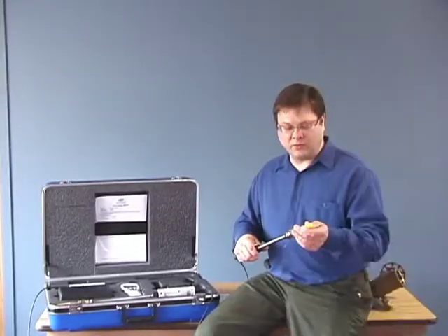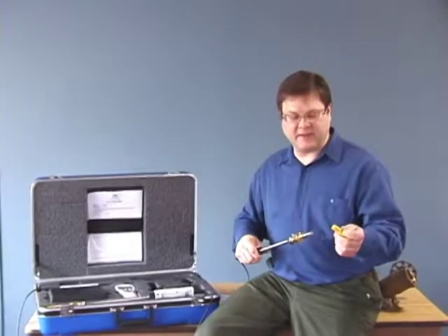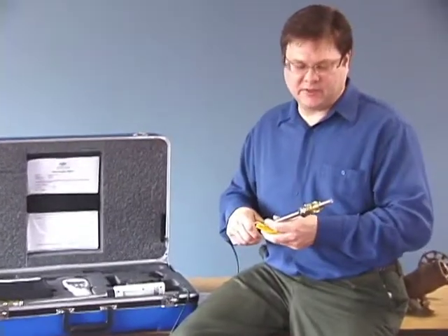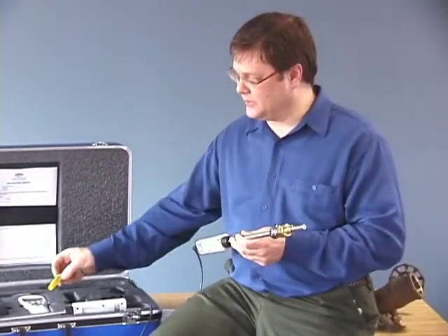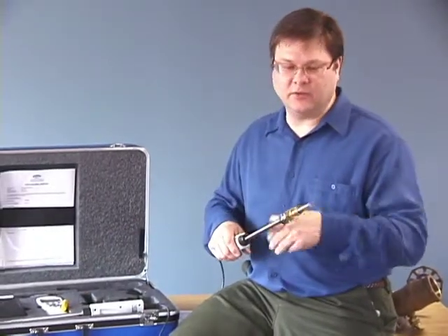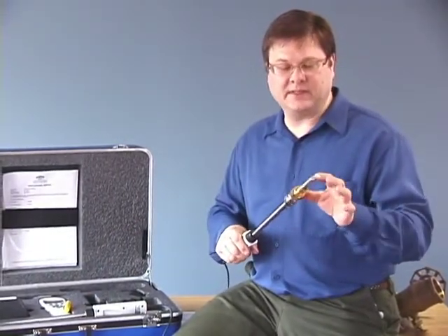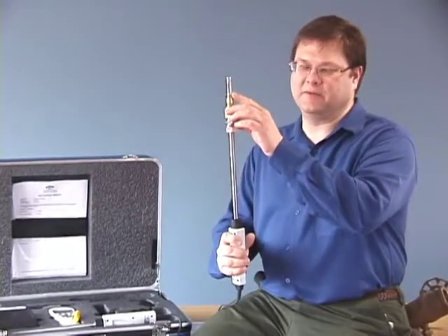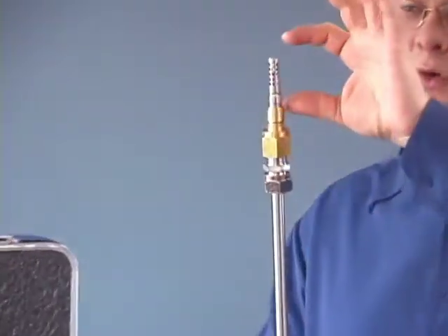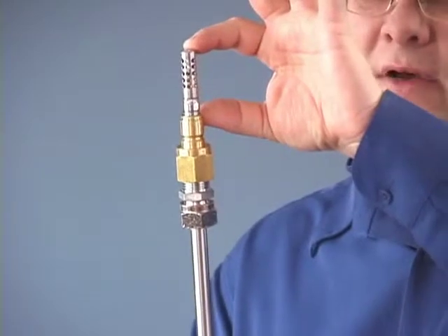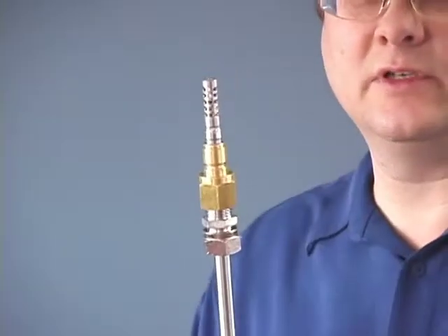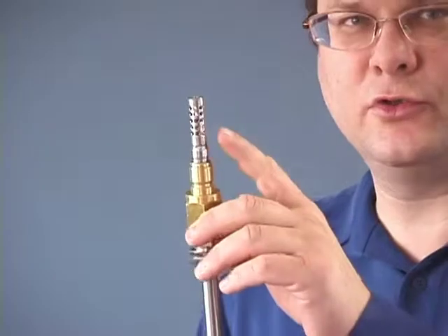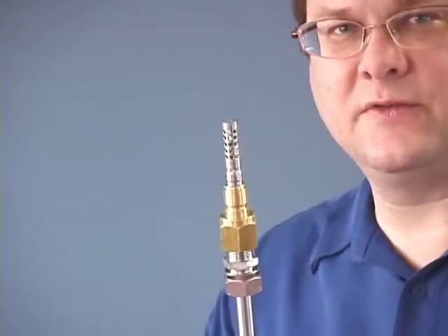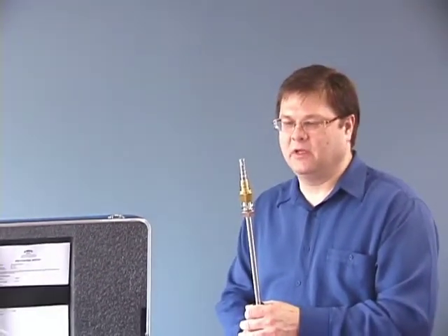As you can see, our oil probe comes shipped with a protective cap. Once it's off, you don't really have to worry about it too much. You can either retain it or you can throw it away, it doesn't really matter. The sensor head is in this filtered area here. So the oil has to be at least above the sensor head in order to get an accurate measurement. There are two sensors in here. There's a relative saturation sensor and a temperature sensor, and combined they are used to calculate the ppm.